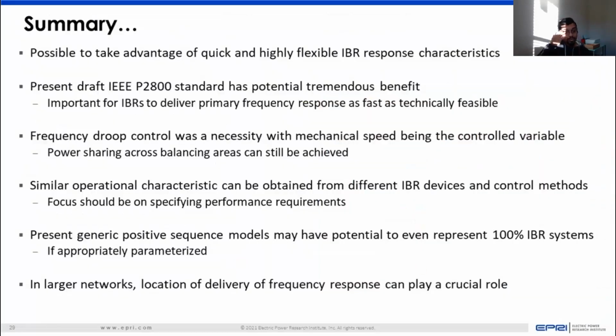So to summarize what we spoke about today: our work has shown that it's possible to take advantage of the flexibility from inverter-based resources, and the present draft standards being developed can have tremendous benefit, as long as we keep in mind certain key points, especially regarding the ramp rate and how fast these devices naturally respond, as far as providing response as fast as technically feasible.